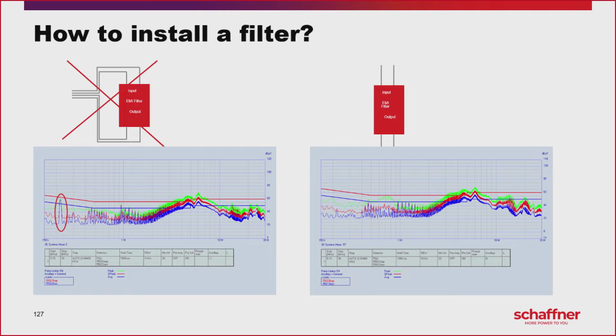Okay. Another example is the saturation. The saturation is not due to the installation issue, it's mainly due to the filter dimensioning. So this is a vacuum pump that we have tested, and we just picked up a catalog filter, and actually we picked up more than one. During all tests, we had a high noise at 100 kilohertz, and we could never get rid of that noise. And it was simply due to the geometry of the common mode choke within the filter. It wasn't the right dimension. It wasn't enough to get rid of the noise. So what we did is that we modified the capacitors within the filter in order to enhance the performance of the common mode choke and enhance the performance of the filter in general.